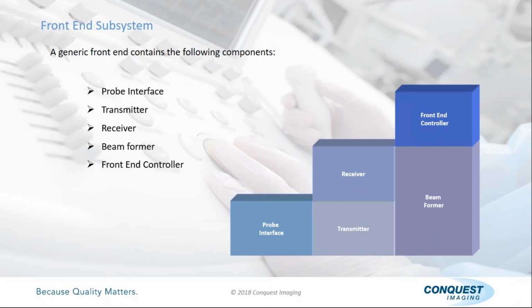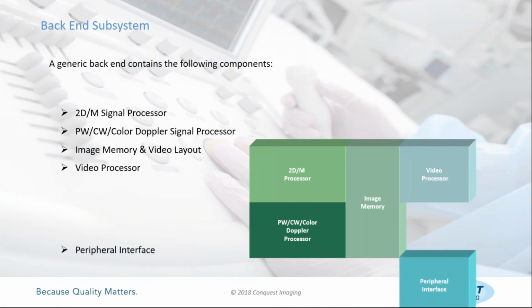After it's amplified and time gain compensated, it passes it to a beamformer, and the beamformer digitizes the information and then sums it all up, all 192 channels, and passes it to the front end controller. Why? Because it's the only board that talks to the back end. We have to digitize the data right here because we're getting ready to send it to the computer, and it only understands digital data, not analog data. So that's how every front end in ultrasound works.